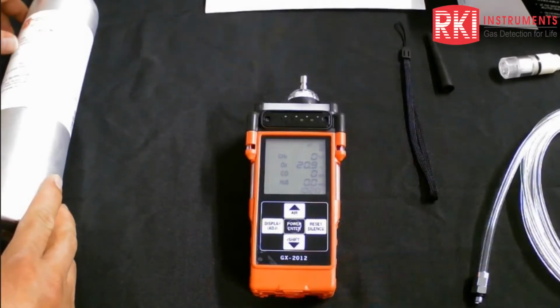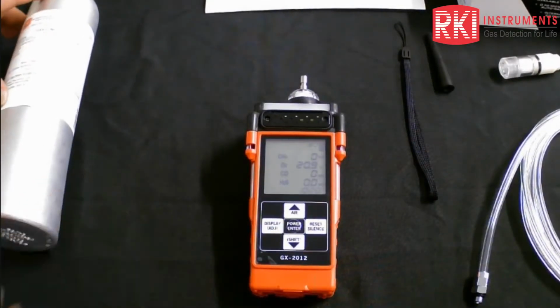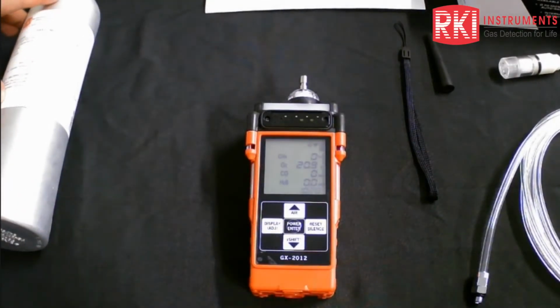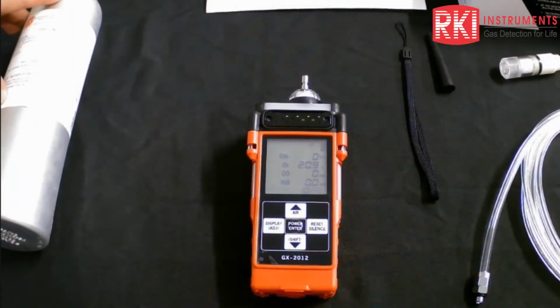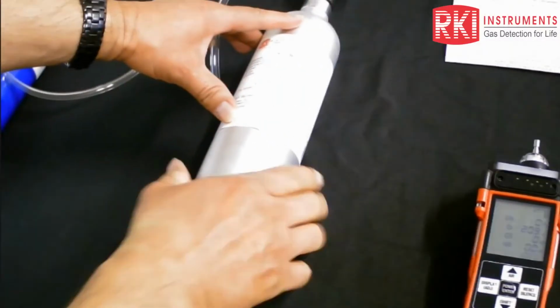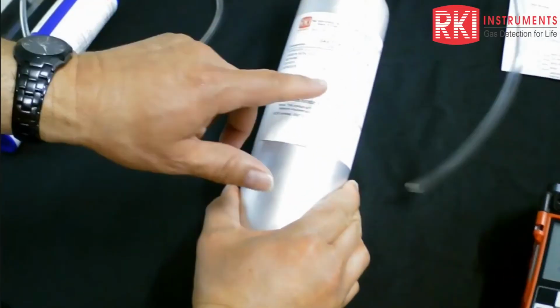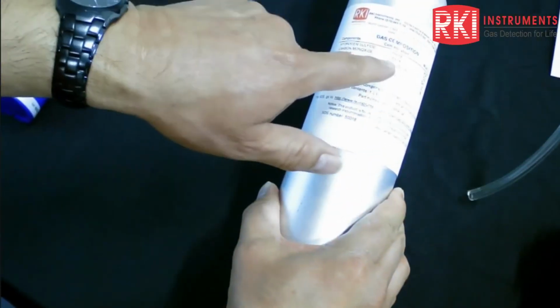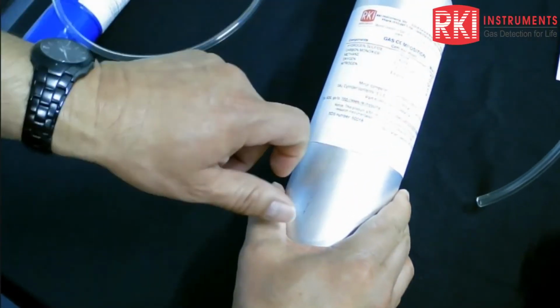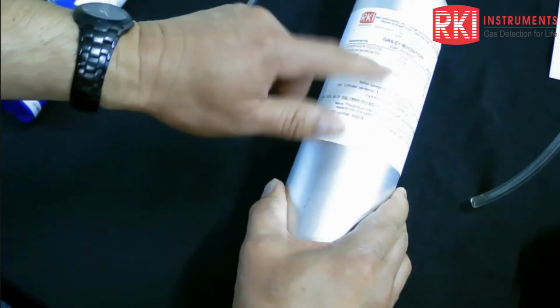Okay, so we'll do a calibration next. I've got a 4-gas mixed cylinder here, 50% LEL methane, which I mentioned is 2.5% by volume. Then I've also got 12% oxygen, 50 ppm of carbon monoxide, 25 ppm of hydrogen sulfide. The balance is nitrogen.